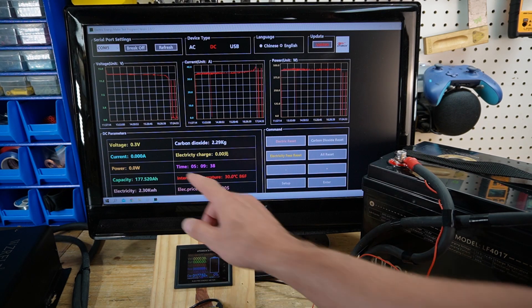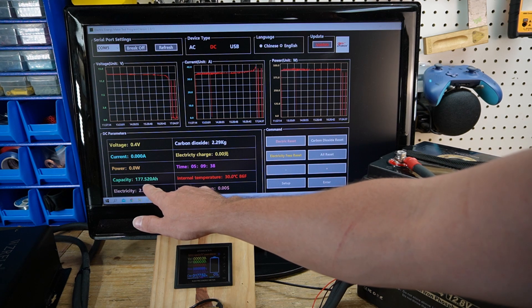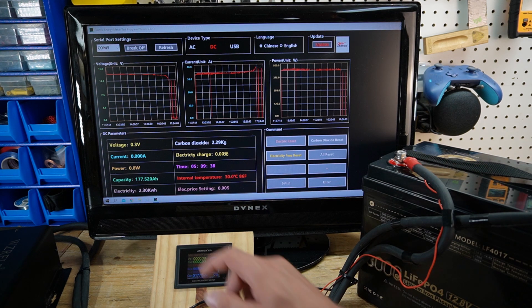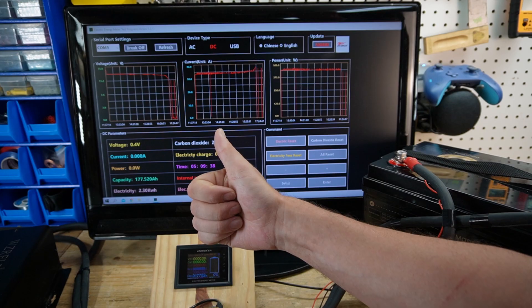The test is complete, and we have a capacity of 177.52 amp-hours, which is 7.52 amp-hours above the rated capacity of this battery. So this test is a pass.